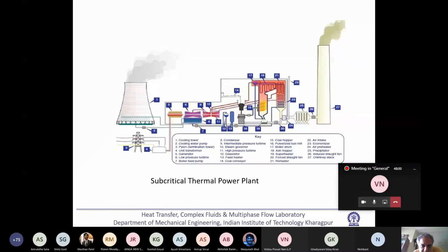Yes? Okay. So you see, here we are getting the coal. Coal is being crushed, and then the bigger chunk of coal is coming over here, which is a hopper. And here there is a ball mill. The ball mill makes it into pulverized coal. In most of the present day boilers, of course, there could be some sort of fluidized bed boiler. We will see how far we can do it. But otherwise, pulverized fuel firing is there.